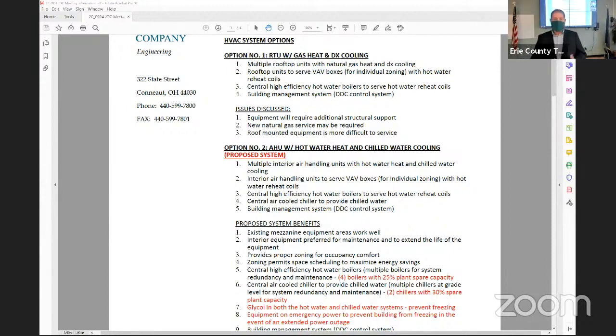Looking at the central boiler plant, what we are proposing with that solution is 4 high efficiency hot water boilers. You would have roughly 25% spare capacity. So if you lost one boiler, you could still, on the coldest day of the year, maintain operation, replace the boiler, and not have any issues.